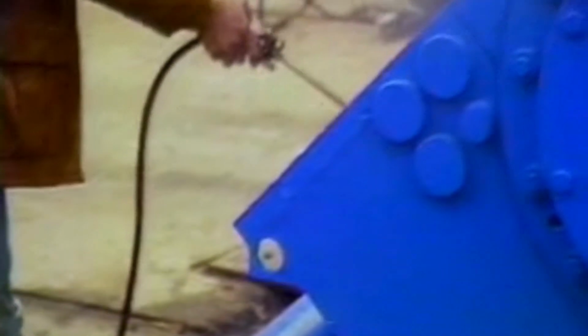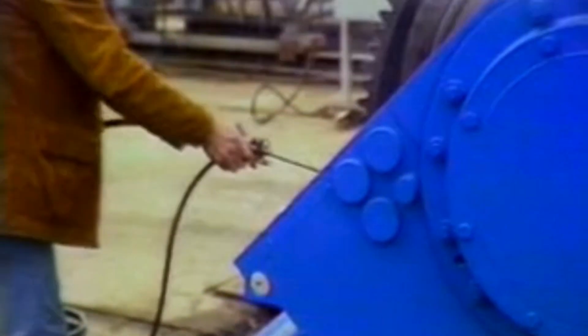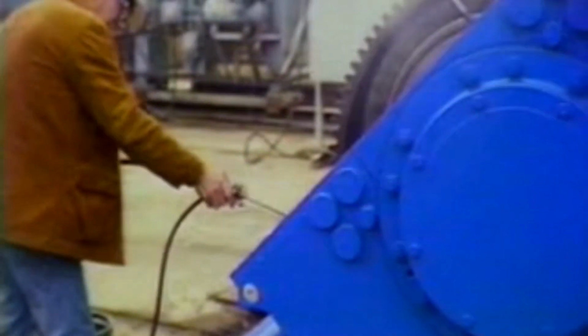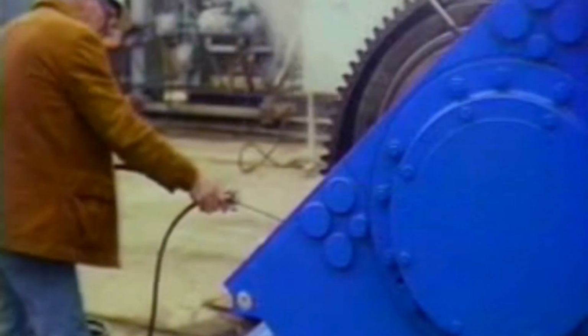Okay, drain the crankcase. Use a diesel spray to loosen any sludge buildup in the bottom of the pump. Pay special attention to troughs and ledges. Now get a bucket of diesel and some rags and clean the pump. Be sure to clean the oil pump suction strainer in the bottom of the crankcase. Take some time here to make sure the pump is very clean. Would you eat breakfast out of it?